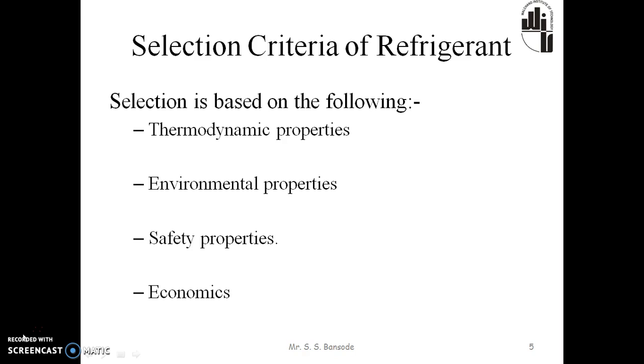Selection criteria of refrigerant. Selection is based on the following points. First, the thermodynamic properties — such as the suction pressure, the discharge pressure, the pressure ratio, latent heat of vaporization, thermal conductivity, and viscosity. The thermodynamic properties are interrelated and mainly depend on normal boiling point, critical temperature, molecular weight, and structure.